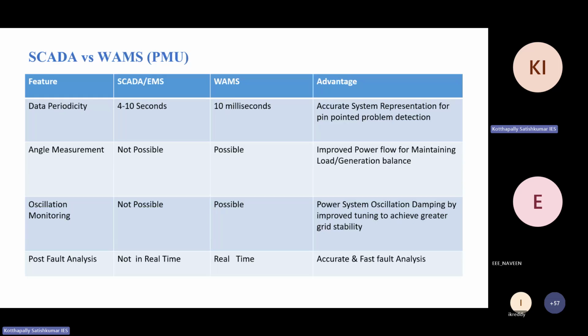Now, angle measurement. In the older SCADA system, it is not possible to measure angle, because to measure angle, both substations should capture data at exactly the same time. SCADA is not a synchronized system while capturing data—for example, one substation may capture data at 7:30, while another captures it at 7 hours 30 minutes and 2 seconds.